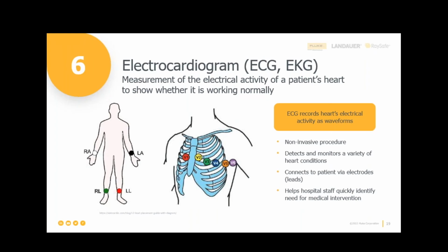We can't do that. You would never be able to afford a test instrument that had that built in, nor could it be very well maintained and sustained, because you can rent those signals, but you cannot buy them, you cannot incorporate them into your system. It's much more difficult than that. So what is the main thing that we care about?